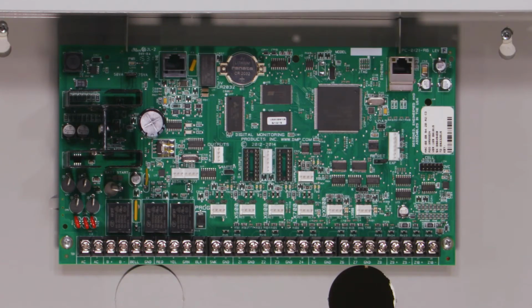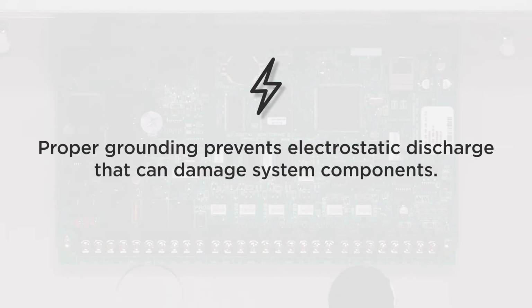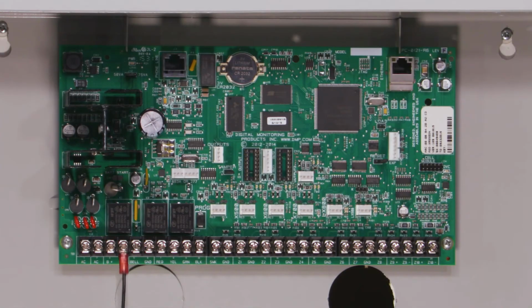Make sure to ground the panel before applying power to any device. Proper grounding protects against electrostatic discharge that can damage system components. The earth ground can be connected to terminal 4 using 14-gauge wire or larger, applied to a cold water pipe or a ground rod.